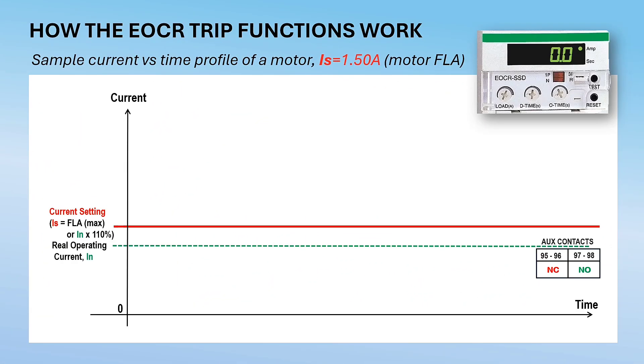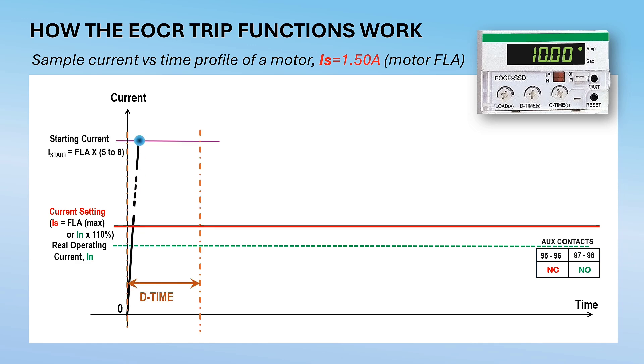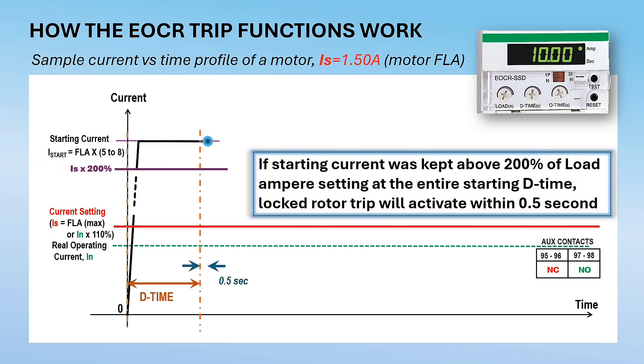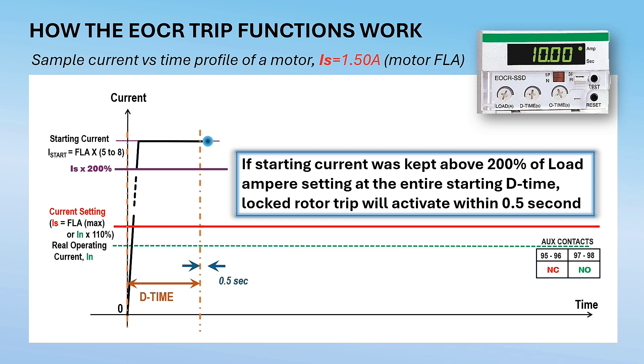Locked rotor trip function: when starting a motor from a complete stop, the motor draws a high starting current. If the motor starting current is kept equal to or above 200 percent of the overcurrent ampere trip setting for the entire delay time or D-time, the locked rotor trip will activate within 0.5 seconds.